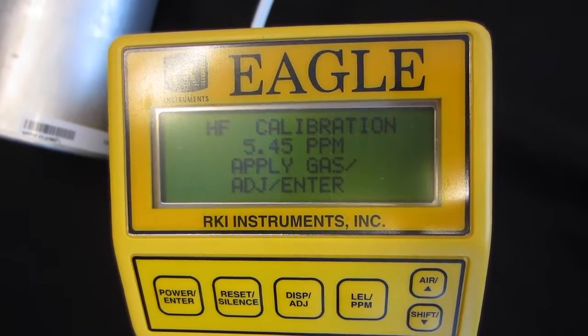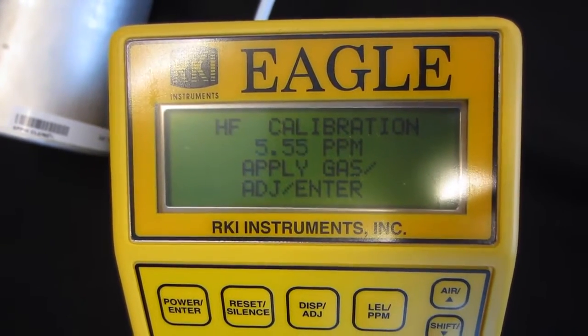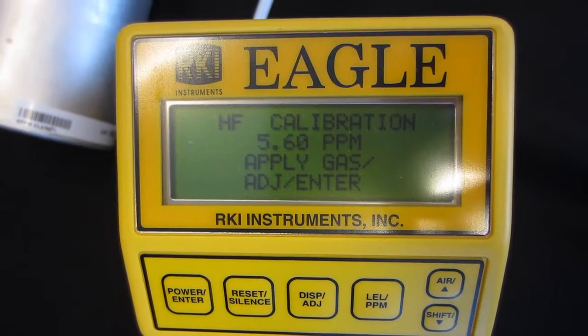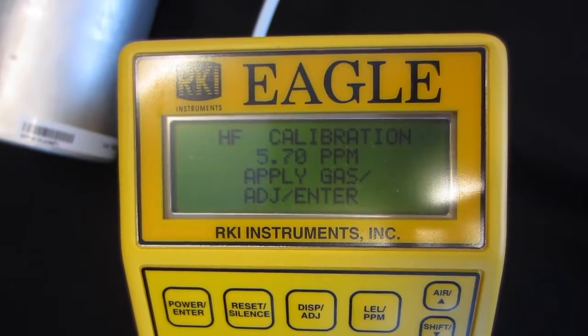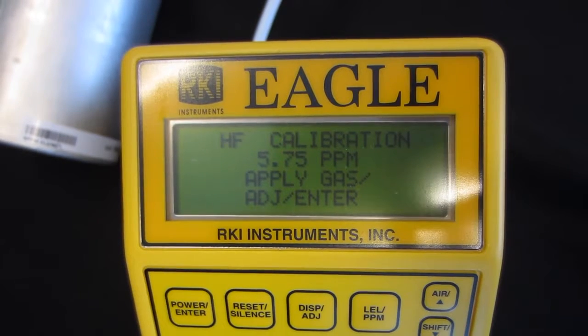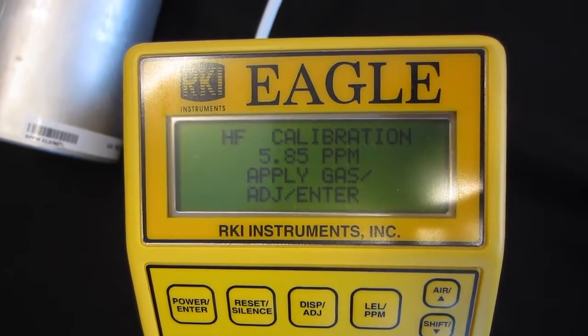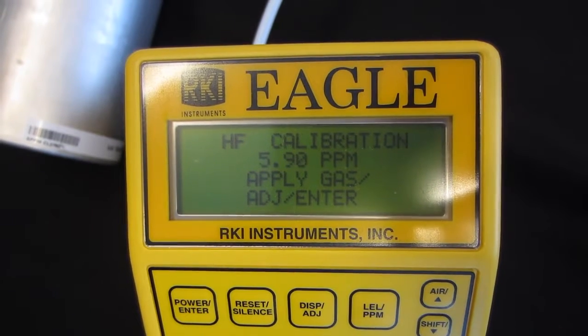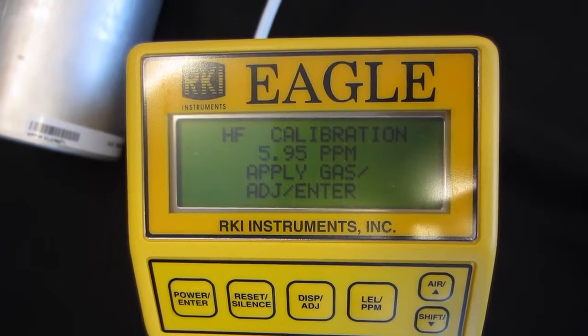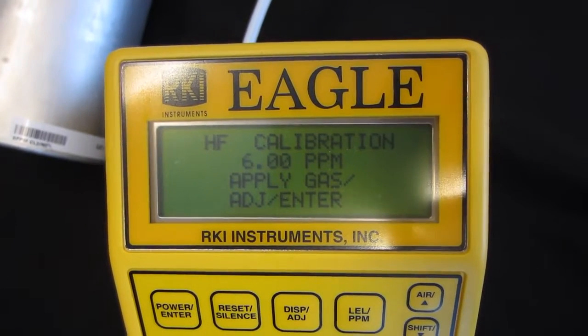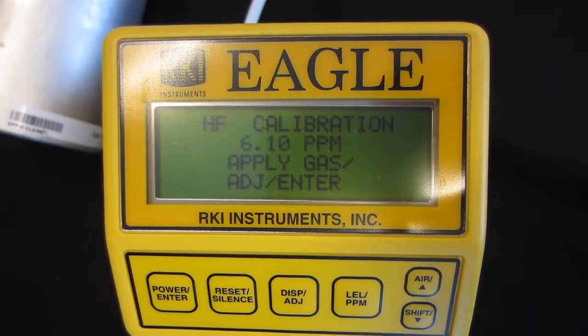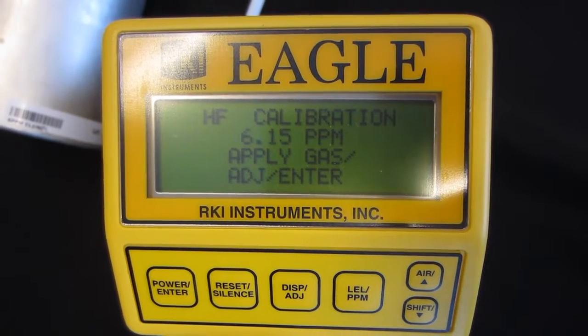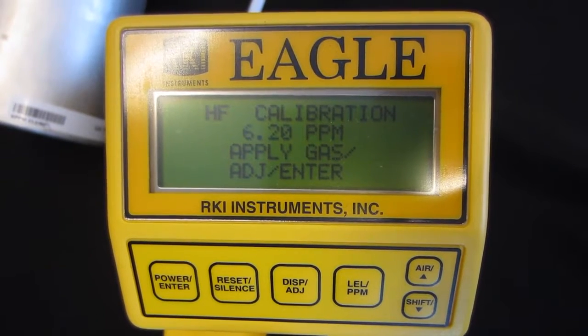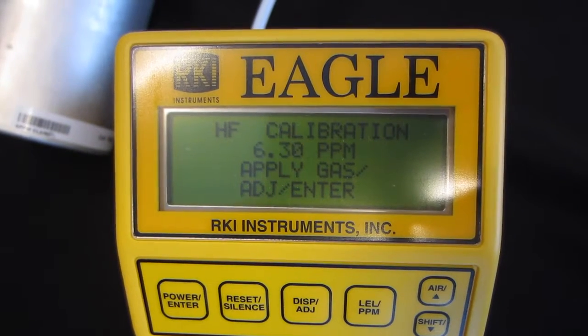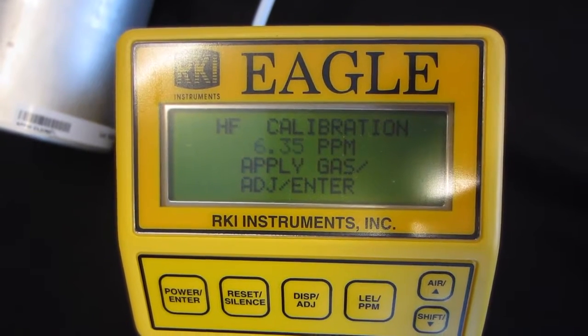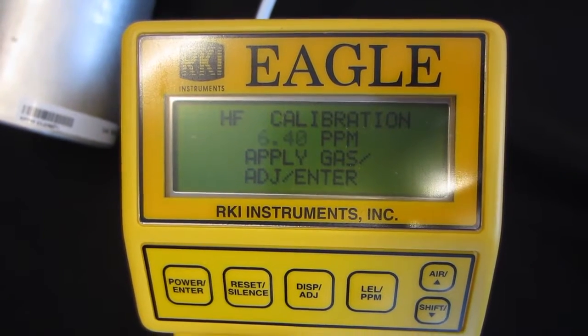Once in a while, we will come across these special toxic sensors. When you do calibrate them, they'll just keep climbing almost indefinitely. And if that's the case, if you get to 2 minutes with the reading still climbing, we'll go ahead and make the adjustment at the 2-minute mark. So again, the rule is generally flow the gas for 2 minutes. If the reading stabilizes before the 2-minute period, then make your adjustment at that point. But if the reading is still climbing, once 2 minutes has been reached, then go ahead and make the adjustment right then and there at the 2-minute mark.